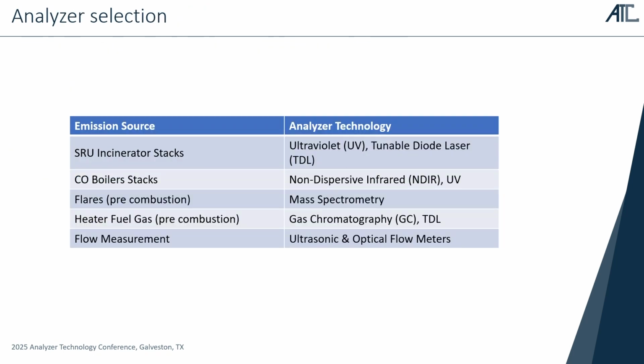Now, although the main point of this presentation is the software that is at the heart of this large CEMS system that combines all these various sources and all the various analyzers, I wanted to briefly highlight some of the analytical equipment that was chosen. Different refineries with different types of combustion devices and configurations selected slightly different technologies based on their requirement to meet these regs, but here are some that were typical. The SRU incinerators and CO boilers were fairly standard, either UV or NDIR. TDL was actually used for some of the SRUs for very hot and very wet gas measurement.